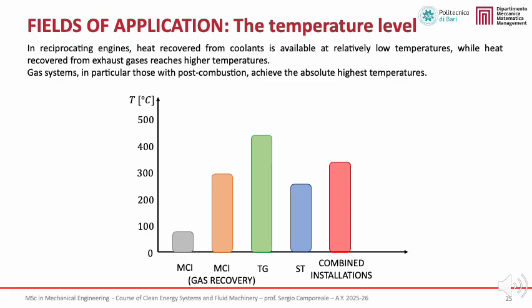In this slide, we focus on the temperature level of the recovered heat, which is a key parameter in determining the fields of application of different cogeneration technologies. In reciprocating internal combustion engines, heat recovery occurs at two distinct temperature levels. Heat recovered from the engine cooling system is available at relatively low temperatures, typically suitable for space heating or low-temperature industrial processes.